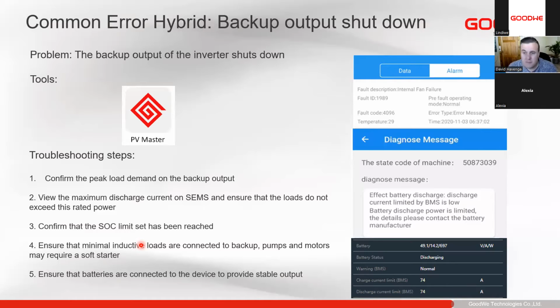Very often it's going to run, no problem, but the wrong inductive load, especially water pumps, cheaper water pumps and things like those, tend to have a very high inrush current because they are starting against a higher head pressure, and that can cause an overload. So sometimes if you do have loads like that, you might require a soft starter or motor starter to mitigate any startup current.